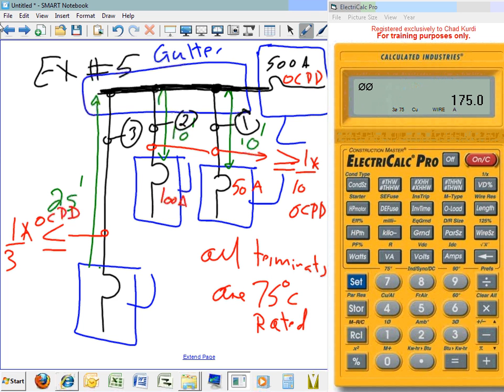Do you guys know why they do it this way? Because if you tap a smaller conductor and you have a short circuit, your conductor, copper or aluminum, and insulation will heat up and evaporate, especially the aluminum, under short circuit condition. It will completely melt and evaporate before the circuit breaker wakes up. It will wake up, but by that time, everything will be mingled together. That's why they want a minimum conductor size that can handle short circuit. And we'll talk about the short circuit rating as we go through the industrial, guys.